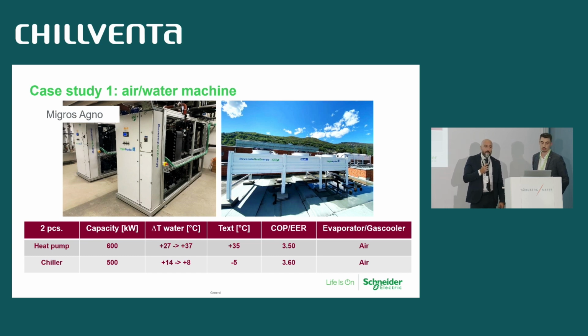The COP and the energy efficiency ratio are indicated in this chart, and the external evaporator gas cooler in the same devices. Even this kind of device has been properly developed thanks to the collaboration with Luve. So in that same device, we have a double coil able to run in evaporator and gas cooler mode to optimize even the defrosting cycle.